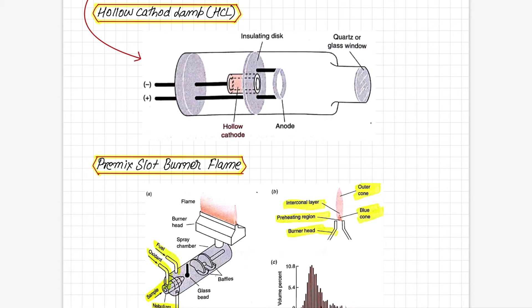So we need different lamps. When we do analysis, we need to change the lamp. This is a little disadvantage which makes this process a little bit expensive. But today the instruments are designed such that the hollow cathode lamp material contains more than one element, so we can analyze four to five elements. This was the basic diagram and outline of the hollow cathode lamp and you can know why we are using it, its function, and why we only use hollow cathode lamp in atomic absorption spectroscopy.